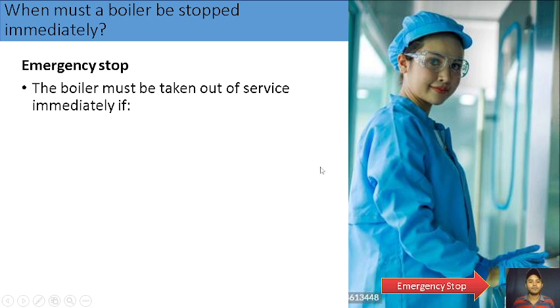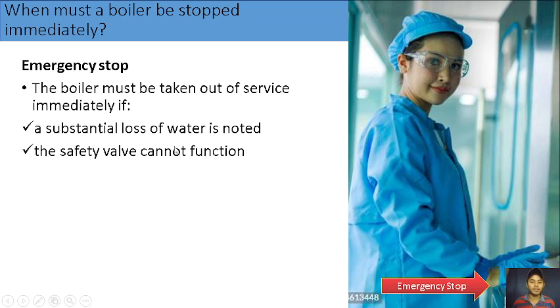Okay, so when you have to stop a boiler, you have to activate the emergency stop push button. The boiler must be taken out of service immediately if a substantial loss of water is noted. So when the water runs out, or when the water is low, you have to stop the boiler. Next, if the safety valve cannot function, the safety valve of the boiler, which protects the boiler from overpressure and damage, then you should stop the boiler immediately.